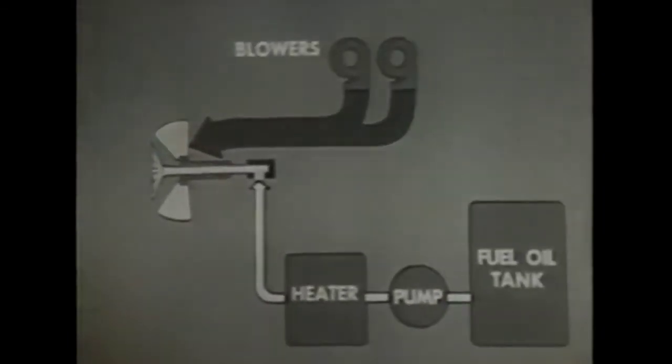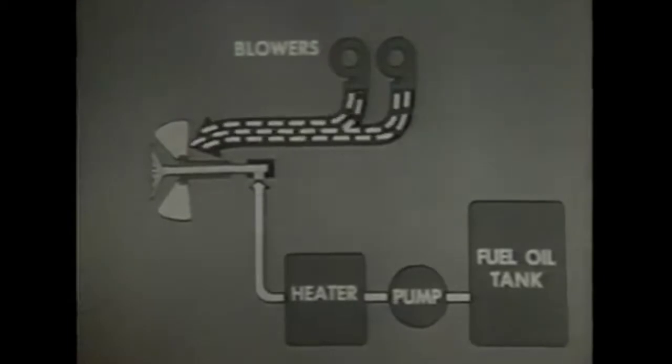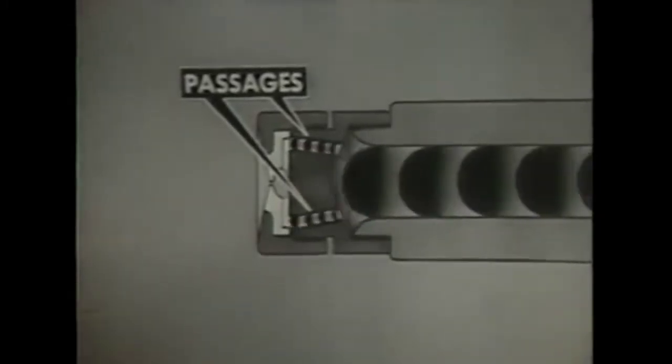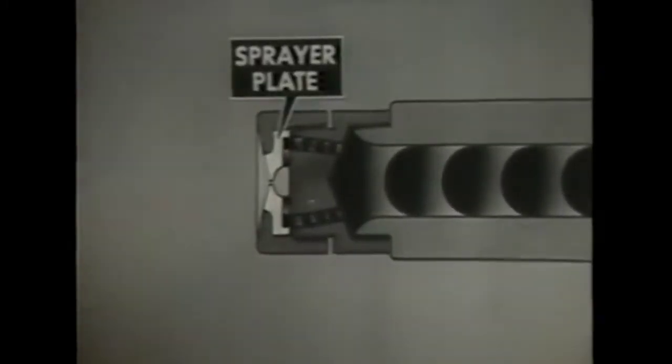The forced draft blowers send a strong blast of air to the burner. The fuel oil pump sends the oil through the heater where the oil is heated to give it good flow quality. Then the oil is pumped to the burner. This simplified cutaway of the burner shows how the fuel oil is forced through the burner barrel to the atomizer nozzle, where a series of passages guide the oil to the sprayer plate. The sprayer plate makes the oil rotate at high speed, breaking up the oil into particles. The oil leaves the atomizer as a hollow, mist-like cone or spray.